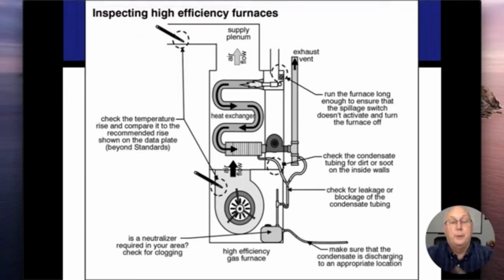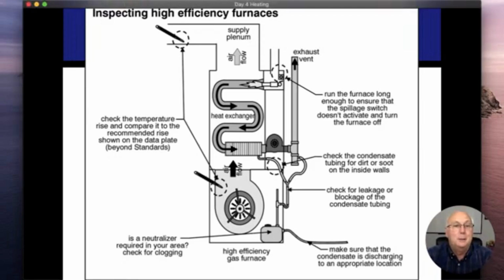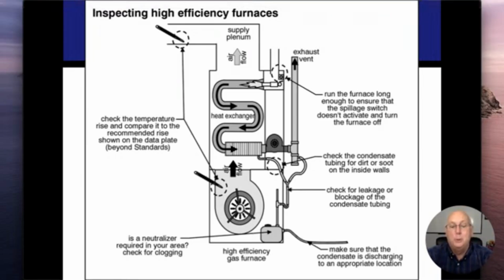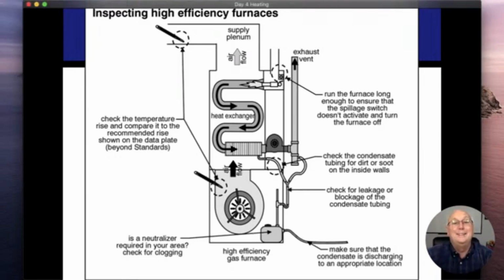Things that we want to look for. We know we're going to create a lot of condensation, so we need to collect and drain that condensation properly. You're going to find a few different areas where they collect, and those things do crack, whether it's from temperature changes or whatever, and because of which they leak. Look for the water, look for the rust, look for all the problems where the tubes are disconnected. We don't use neutralizers in our area. I've never run into one anyway, and it should go into the floor drain. If there's some reason in your area that you become aware that you do have to use a neutralizer, that's what the tank is for on the bottom. I don't know what you would put in there and how often you would have to put it in there, but just know what it is.